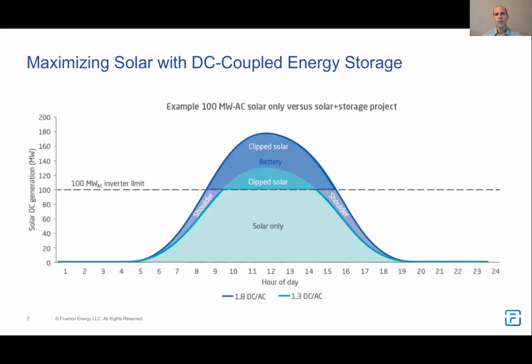Then, rather than clipping that energy in the middle of the day, because the battery and the PV are on the same DC bus, you're able to capture that energy so it doesn't actually get clipped. You can have it flow into the battery in the middle of the day, then time shift it until another part of the day and dispatch it later. So in addition to making the system more dispatchable and flexible, you can increase the amount of energy output for the same amount of interconnected megawatts.